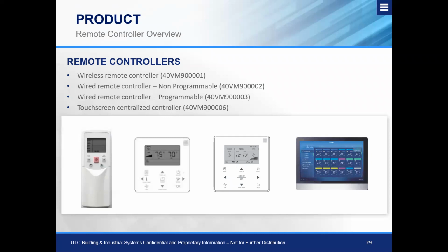Now, if we move on to our wired controllers, we have our programmable and non-programmable types. Depending on what application you're looking for, whether you have a centralized controller, may dictate whether you want a programmable or a non-programmable. And 9 times out of 10, these are typically the local controls that we're going to see mounted on the wall, not only because they offer control of the mode and the set point, but they also offer insight to be able to troubleshoot the system. That's how we get into the system to do addressing. And then, of course, you can set up your time, your clock, and any schedules that the customer wants to set on those as well. So they are multifunctional in how we can use them.